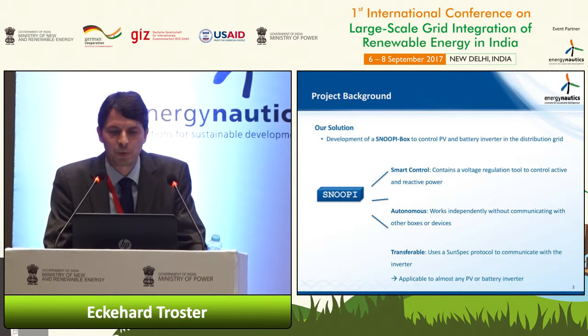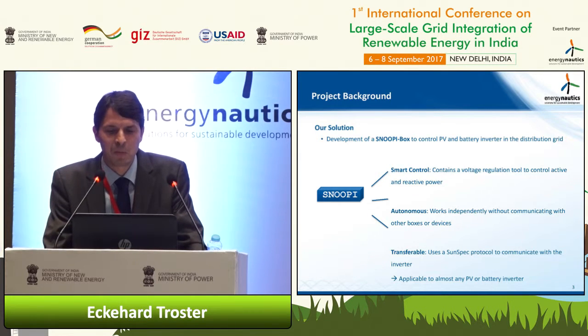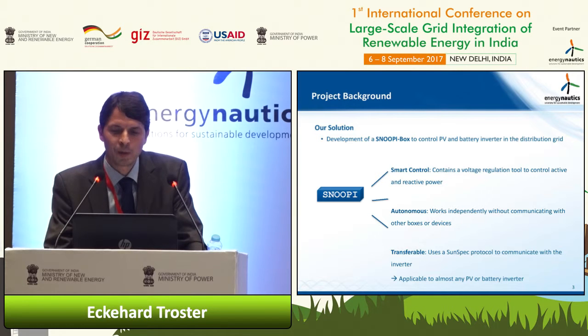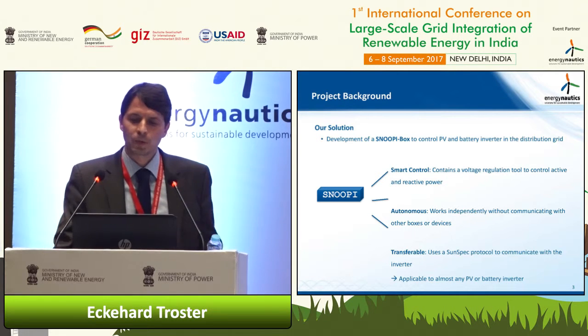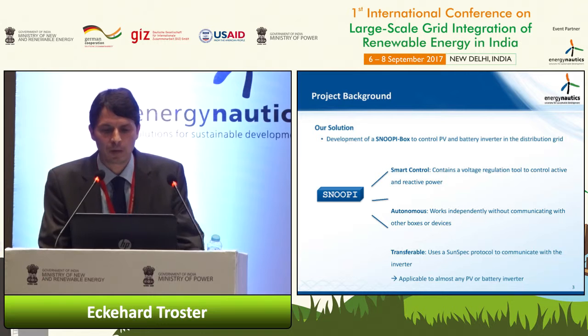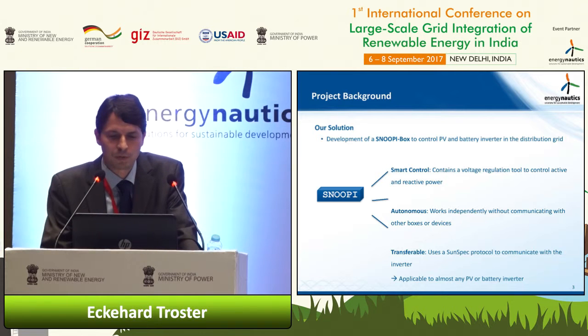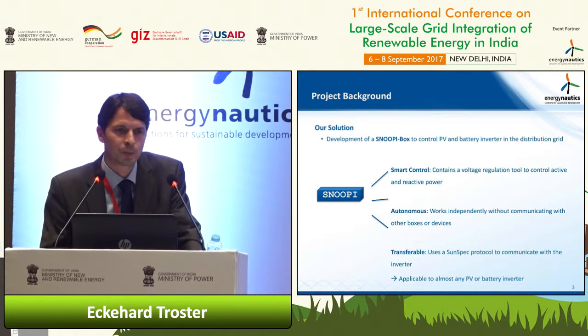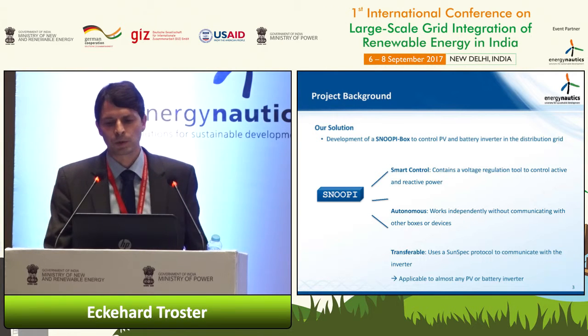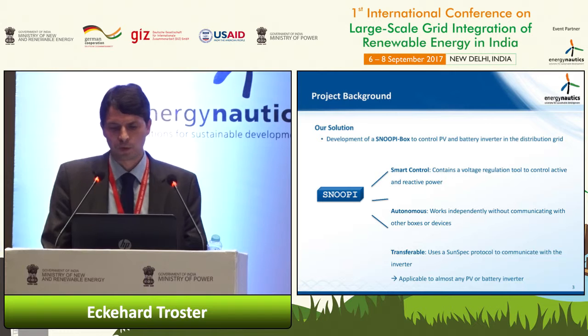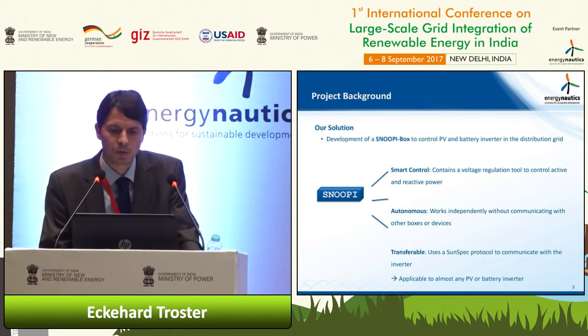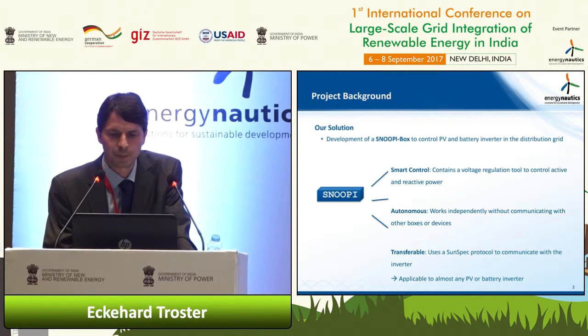We called it SNOOPI, mentioned earlier, or the SNOOPI box. The idea is basically to control the voltage autonomously, with no real communication—that was the main idea—and it should be transferable. So we use the SunSpec protocol, which communicates with the inverter, making it applicable to almost any PV or battery inverter.